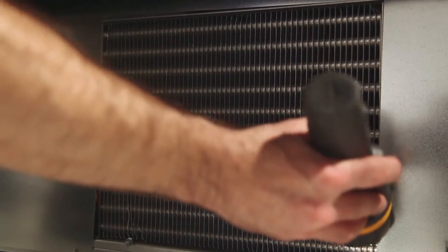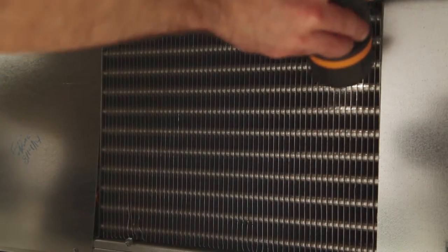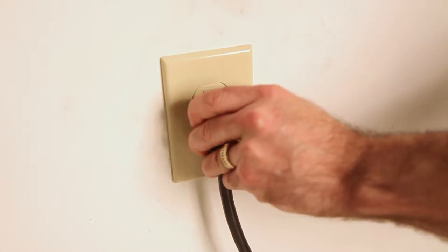Finally, shine a light through the condenser. You should now be able to see light on the other end, meaning the condenser is now free of debris. Then reinstall the grill. Connect the unit to the power and make sure the compressor is running.